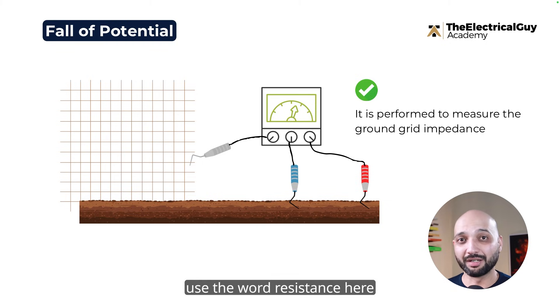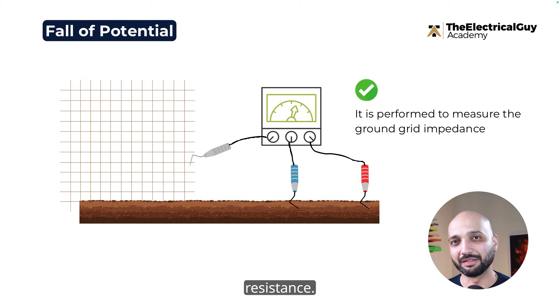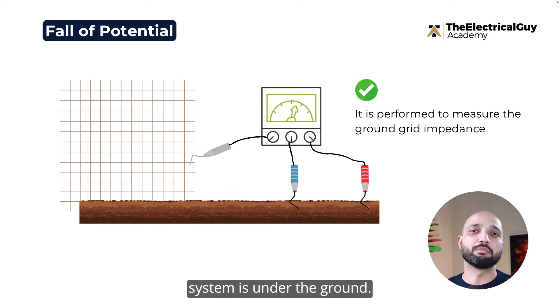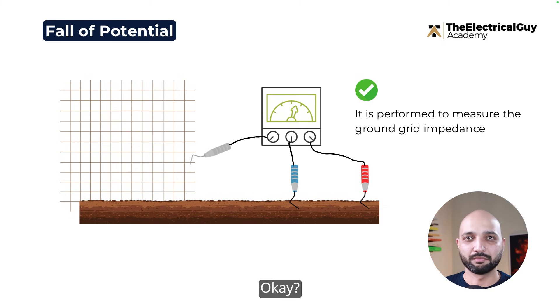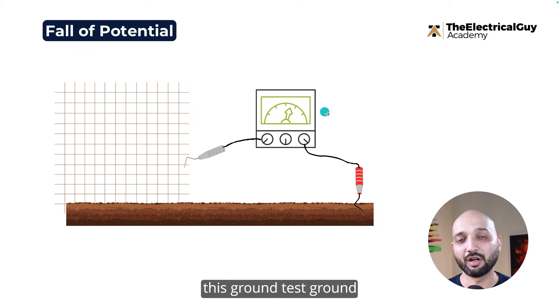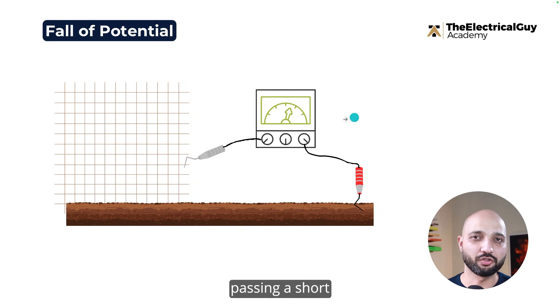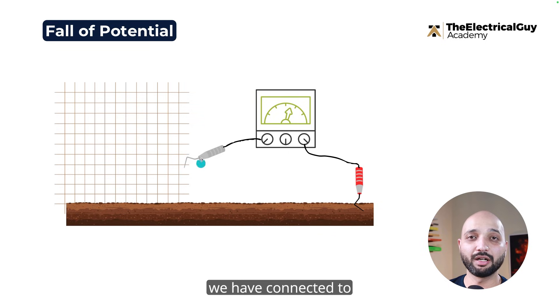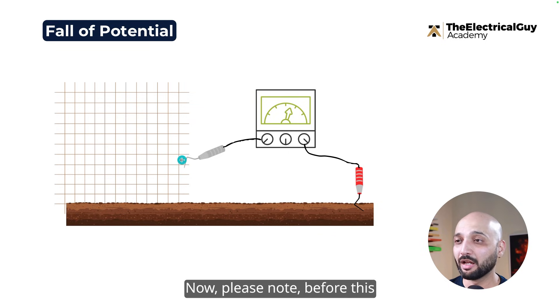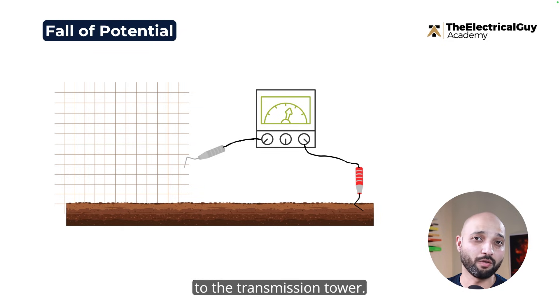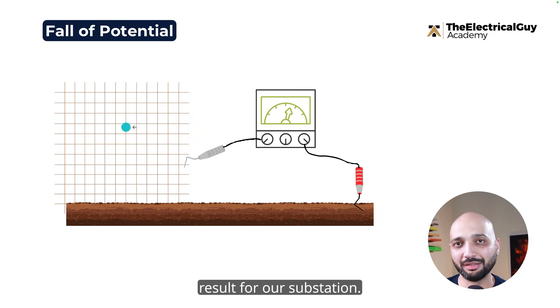We can also use the word resistance here, because what we are checking is the copper wire's resistance. We take a ground impedance test meter capable of passing short current waves. One electrode is connected to the earth grid. Before this test is performed, it is important that you disconnect the earth grid from any other grounding system — for example, if the substation grid is also connected to transmission towers, you should disconnect that to get accurate results for your substation.